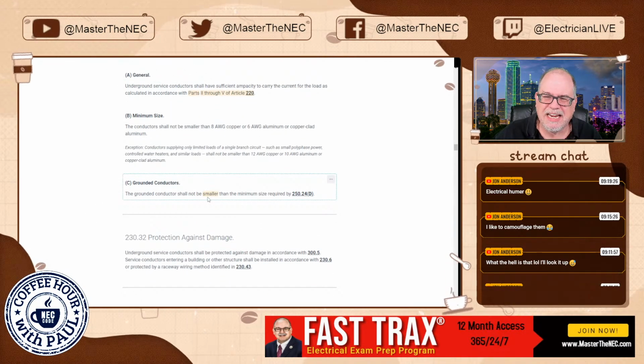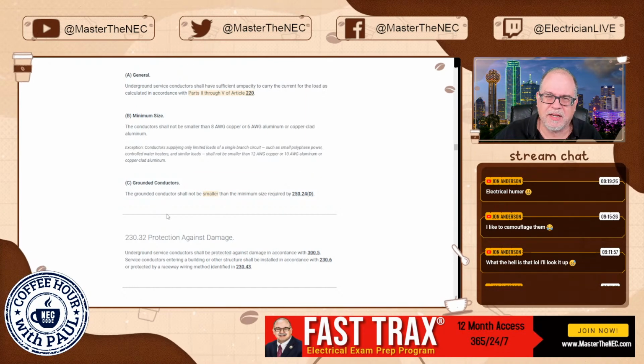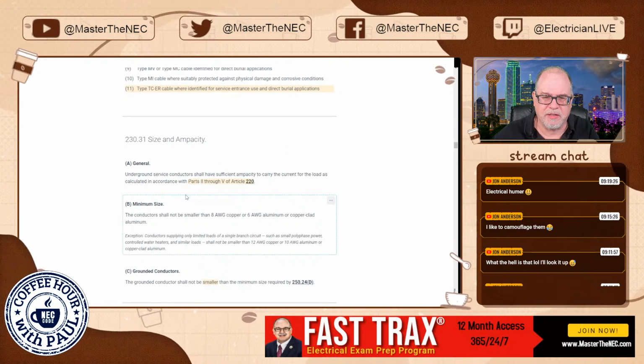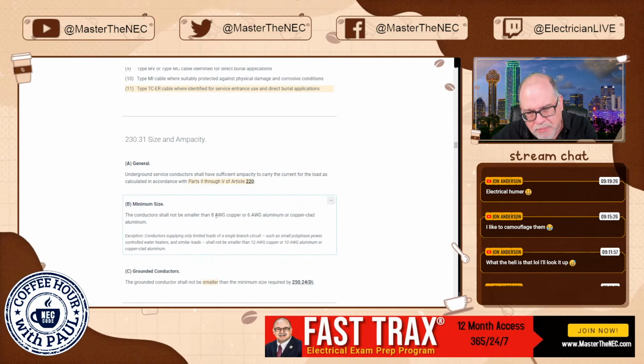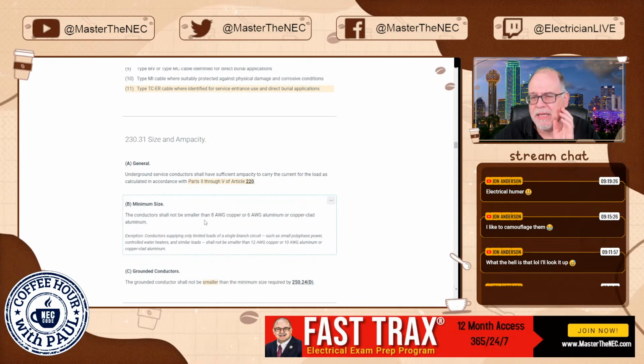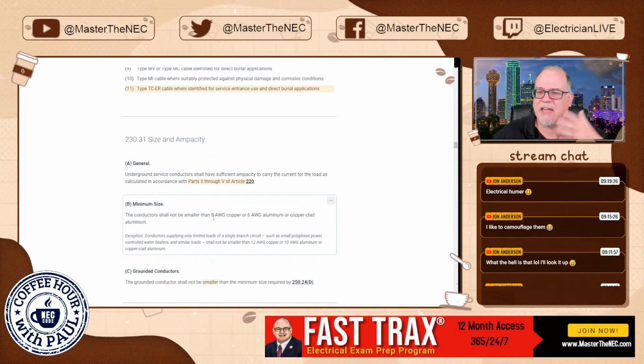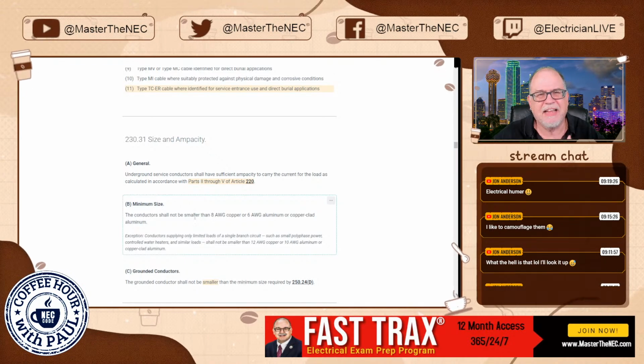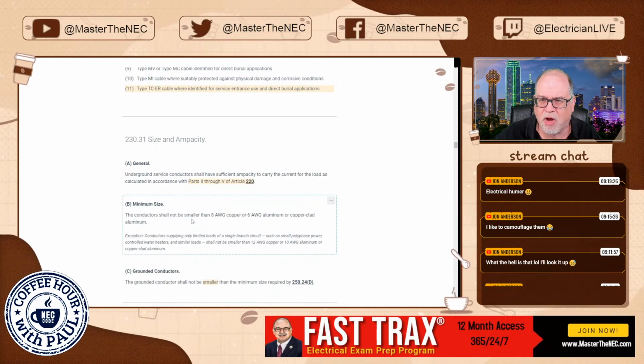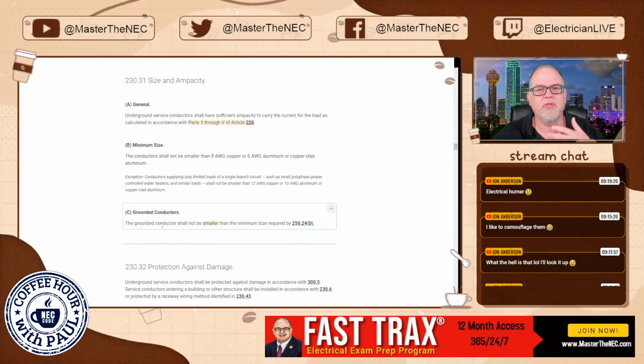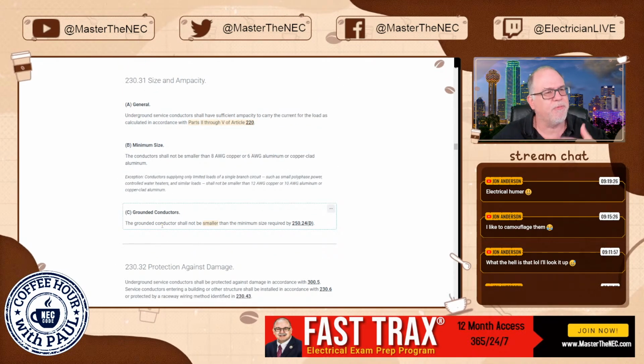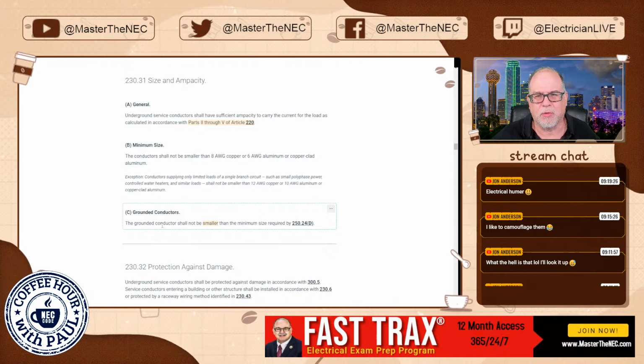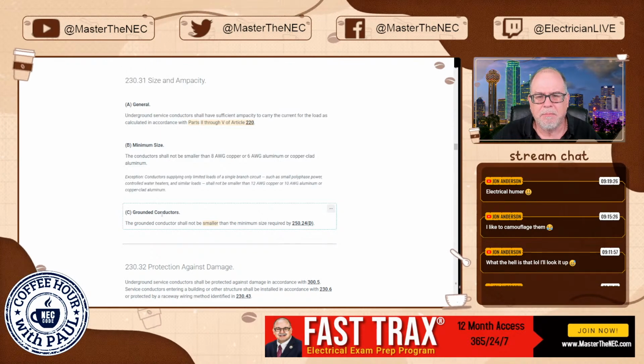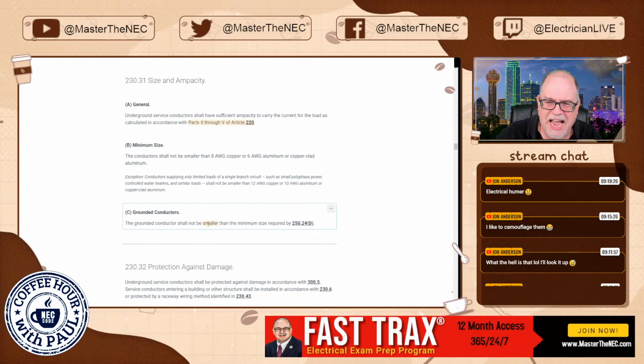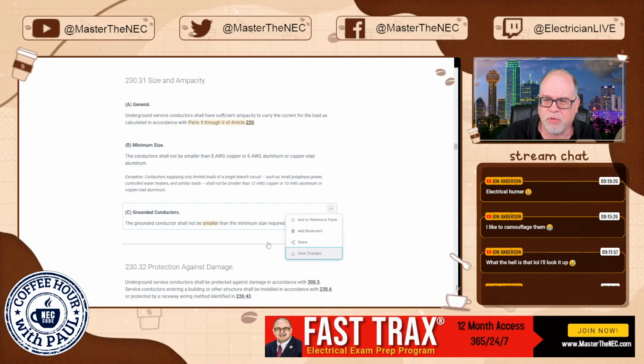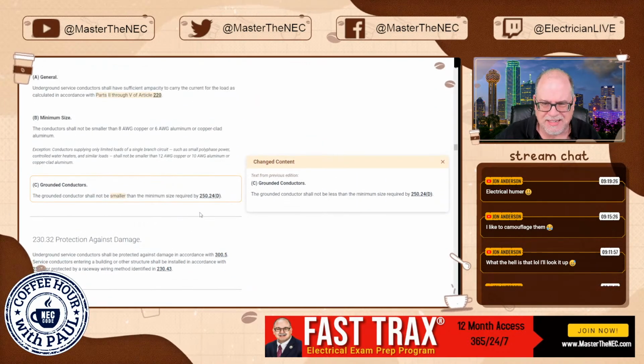Language. So right here, you see they added the word smaller when it comes to the grounded conductor. Now, this is sizing the service conductor. So here's your rules. Here's the minimum size for you folks that are doing exam prep. This is a minimum size. Of course, you still have to calculate the load and whatnot like that. It has to be sufficient to carry the load and all that good stuff. And you're going to use part 2, part 3, part 4, part 5, whatever necessary in order to calculate this service. But when it comes to the grounded conductor, they added the word smaller here, and I just want to show you why that's significant.